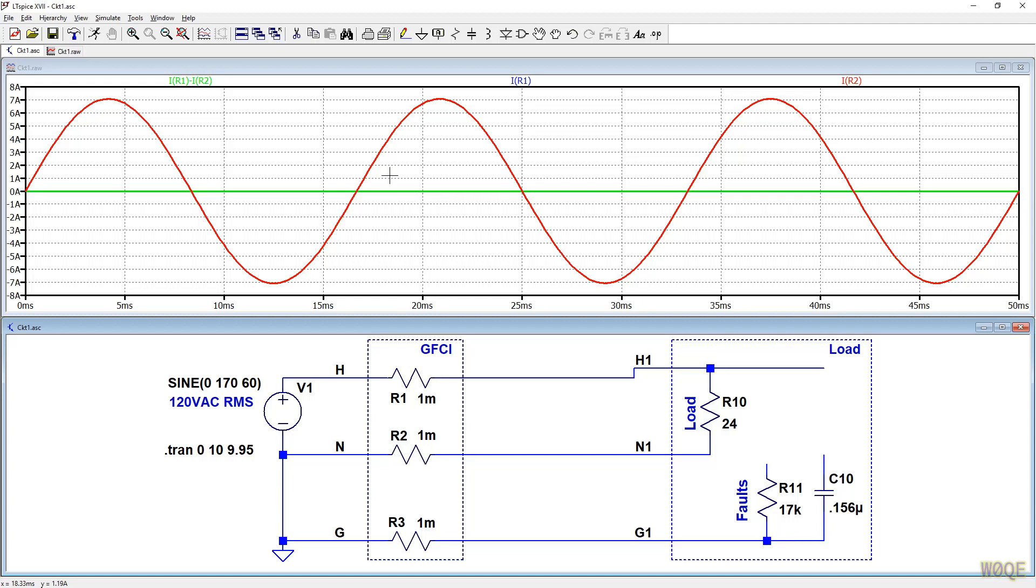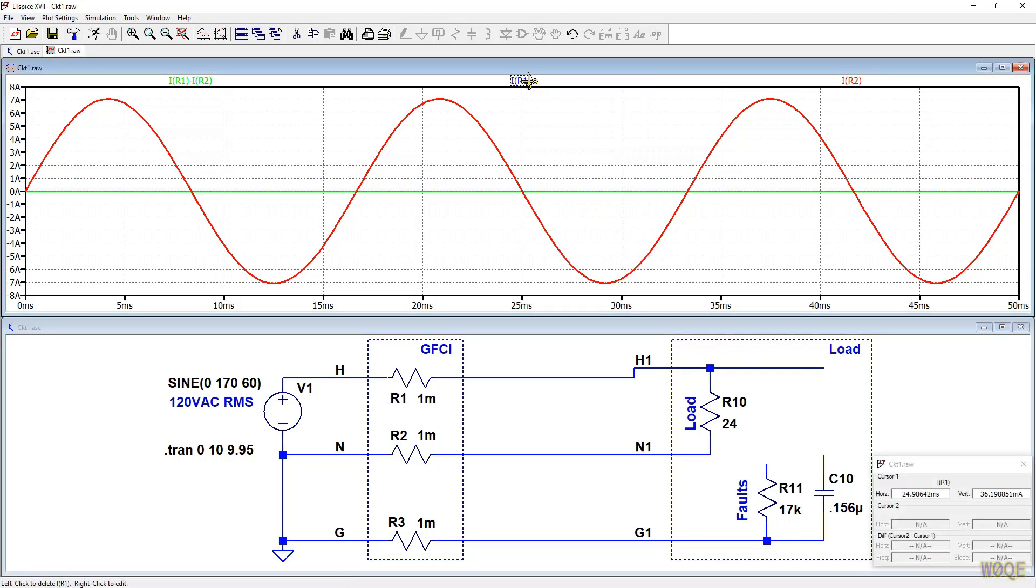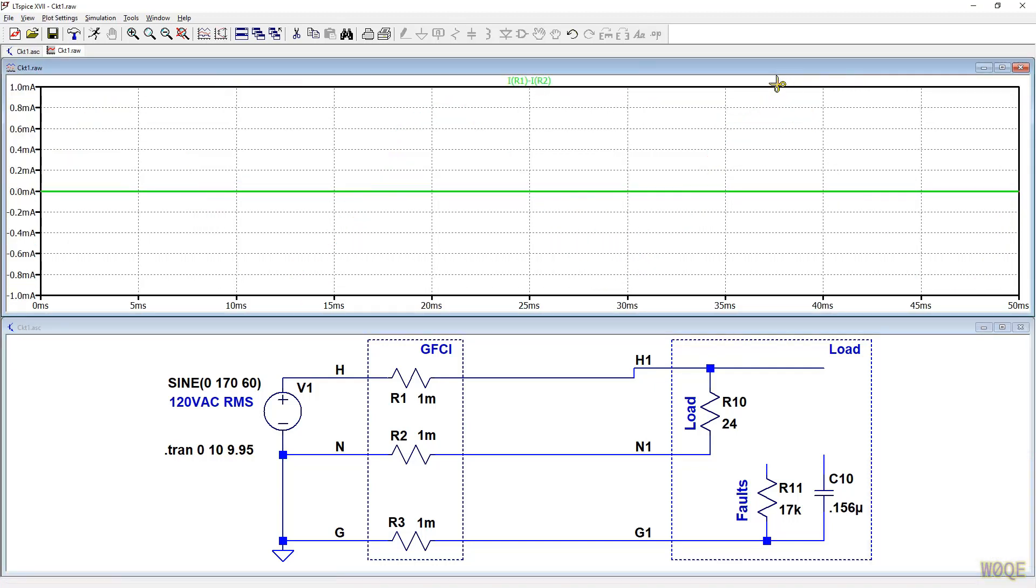What a ground fault interrupter does here is it looks for a current imbalance of about 4, 5, 6 milliamps, something like that. And if it sees that it opens up the circuit indicating that there might be a fault, a leakage fault to ground somewhere.